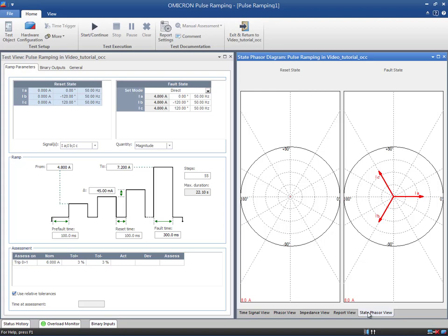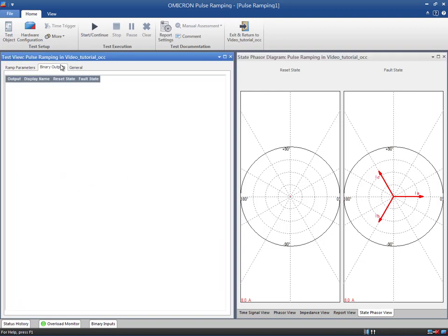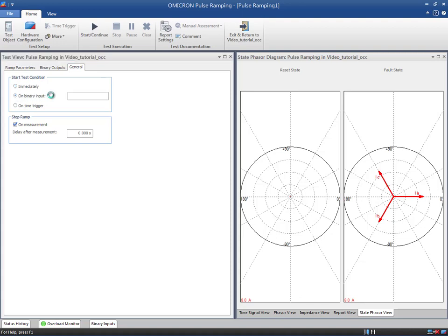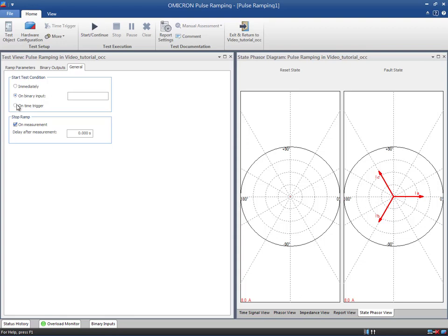Switching to the binary outputs tab, the conditions of the binary outputs for the reset state and the fault state can be determined. In the general tab, we can define how the test should be started and stopped. By choosing immediately, the test will start as soon as the start button is pressed. The binary input option starts the test by the occurrence of a trigger signal at a selected binary input. The last option is used for GPS synchronized end-to-end testing. For this test, immediately will be the starting option.